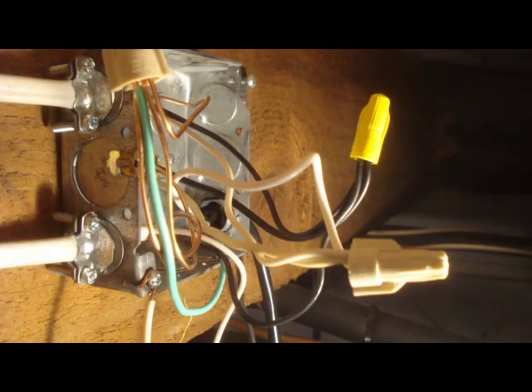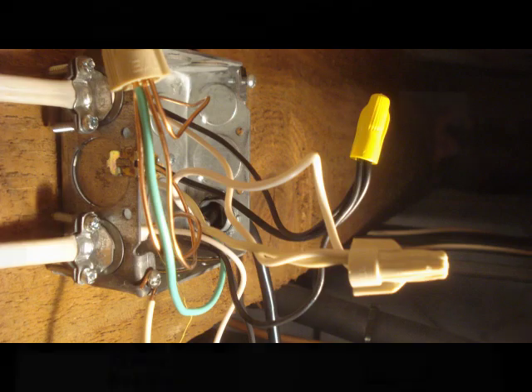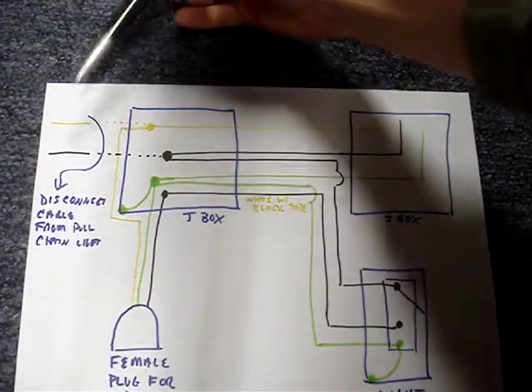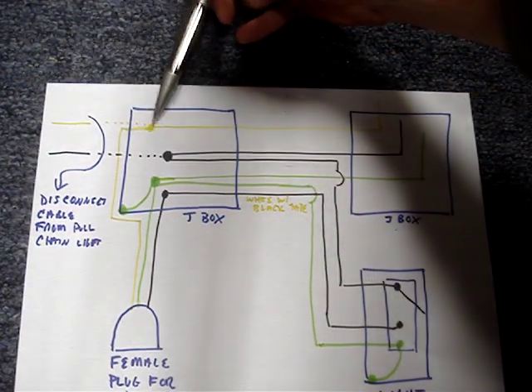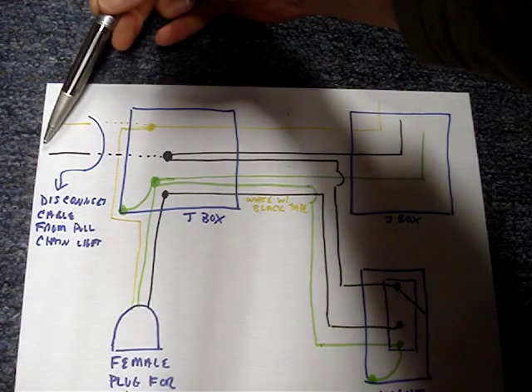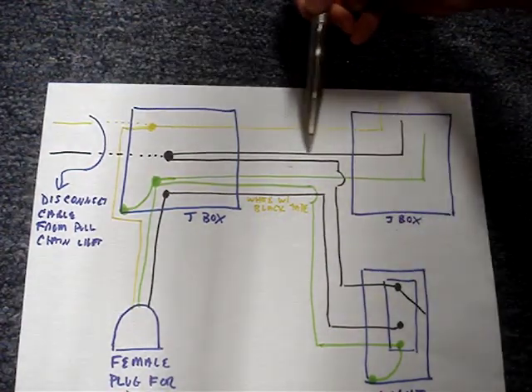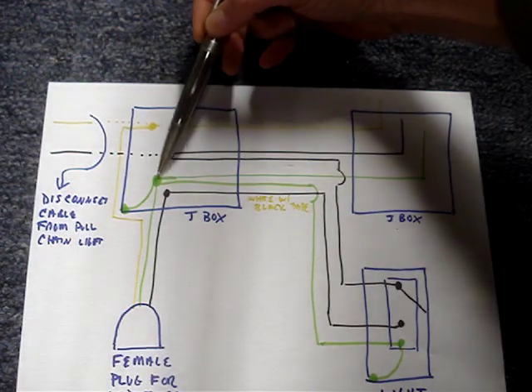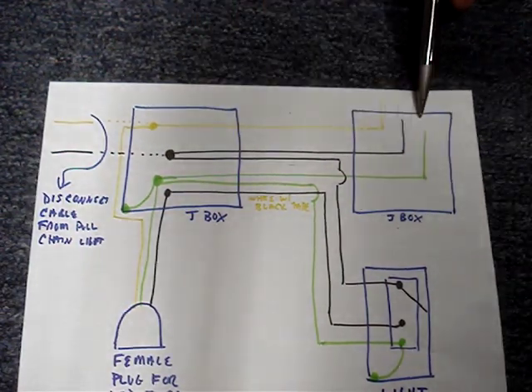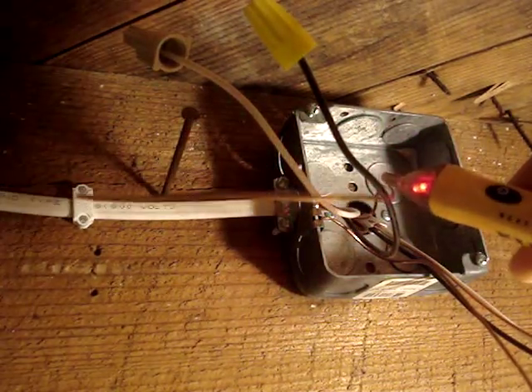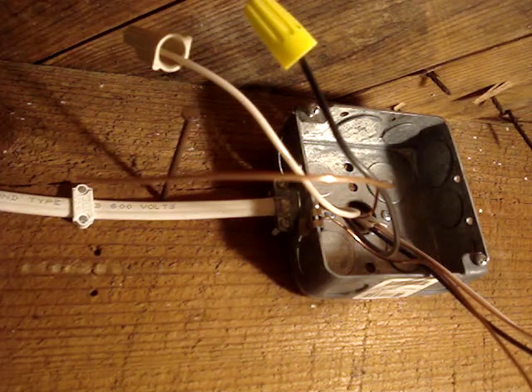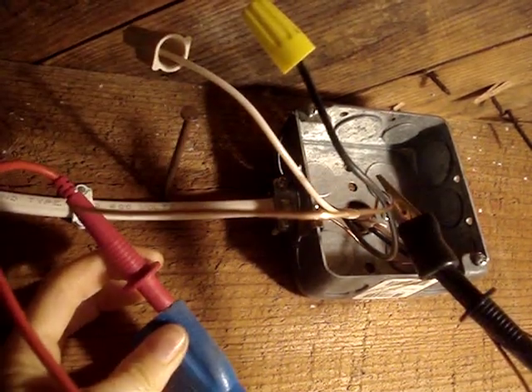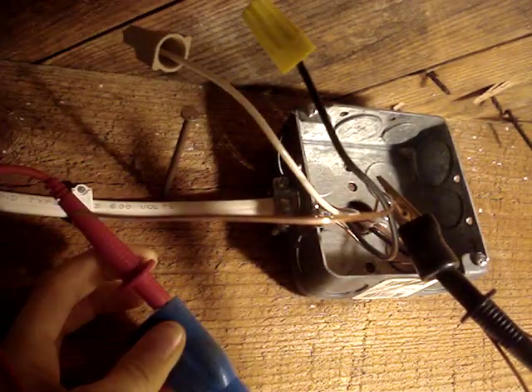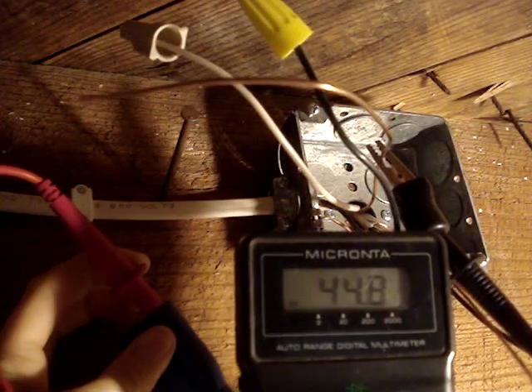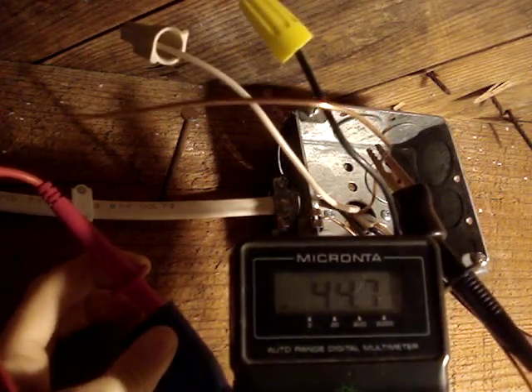Because I don't see any damage to the wire coverings and the box is not overfilled, I suspect the problem is phantom voltage. I left the wires hanging out of this box. I connected the incoming neutral to this neutral. I connected the incoming hot to this hot wire, and I totally disconnected this ground wire. Power is on, and the ground wire is hot. Between a known good ground and the disconnected ground wire, I read about 45 volts AC.